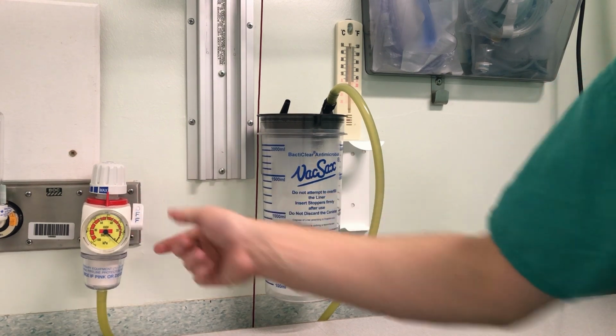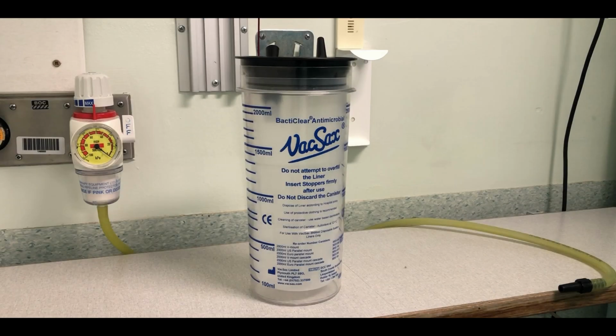Limitations and contraindications. The device should only be used by staff who have been trained and assessed as competent as per the NUH Medical Devices training policy. Ensure that visual and functional checks are performed before use. The device is limited by the canister volume and liner volume, and staff should ensure that the correct size liner is used in the canister.